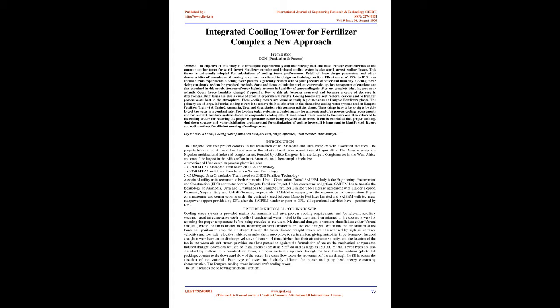Effectiveness of 55% to 85% was obtained from experiments. Cooling tower process is generally related to the vapor pressure of water and humidity. Cooling tower sizing can simply be done by graphical methods. Some additional calculations, such as water makeup and fan horsepower calculations, are also explained in this article.